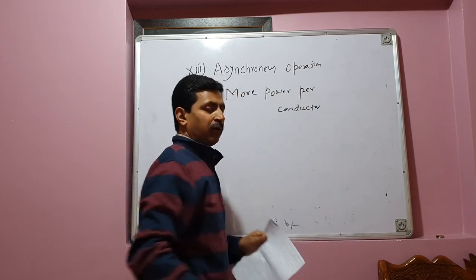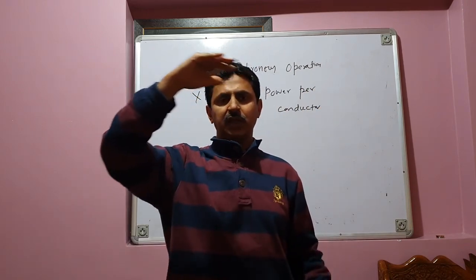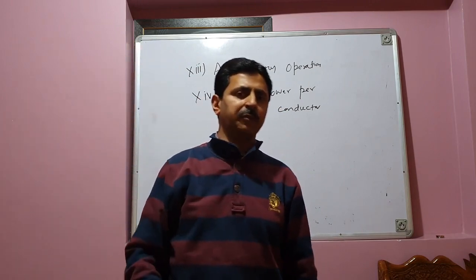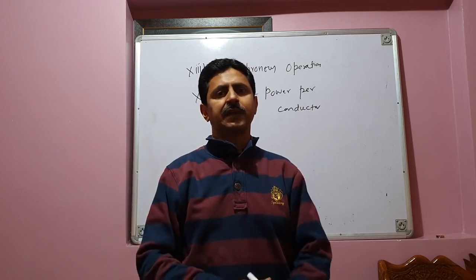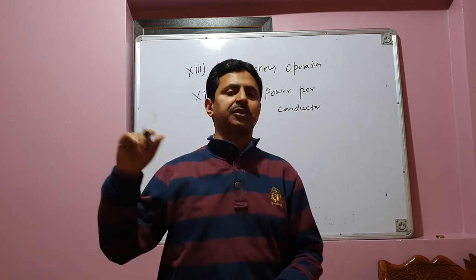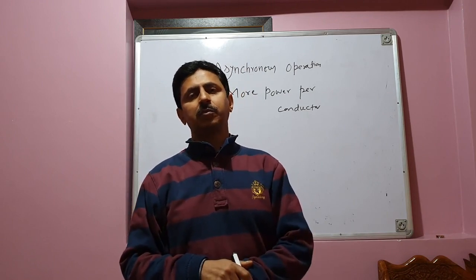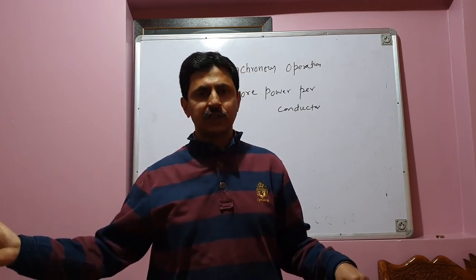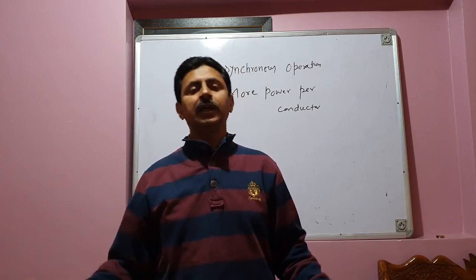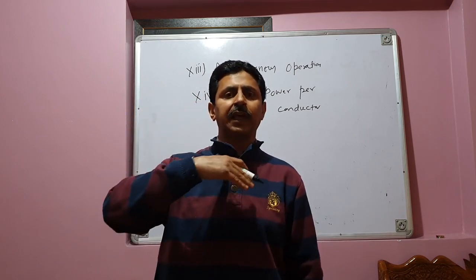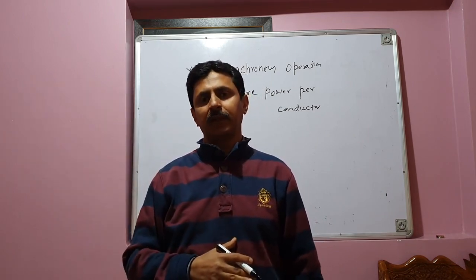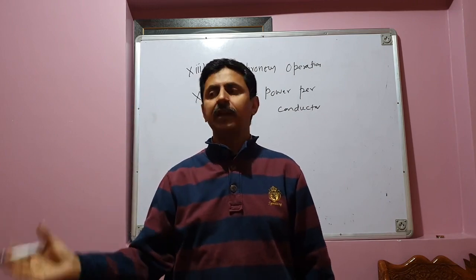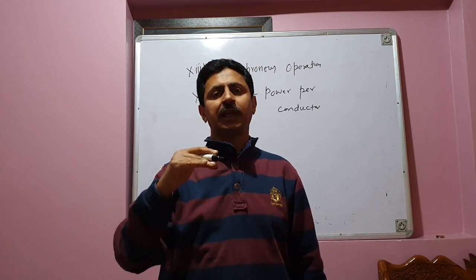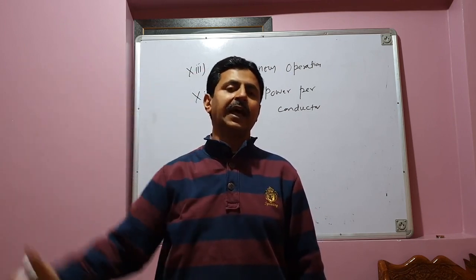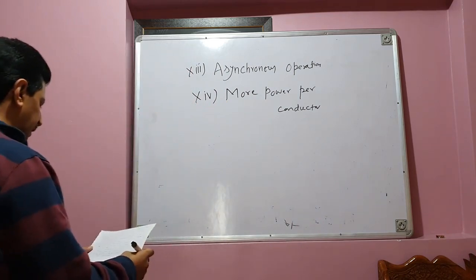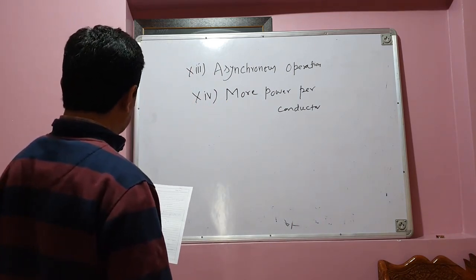I have already told you that in AC transmission there is a limitation because of stability, and line reactance puts a limitation over the amount of power that can be transmitted over the line, and you can never load the transmission line up to its thermal limit. That is not the case with HVDC power transmission system. Length is not a constraint and stability issue is not there. Therefore, you can load the DC transmission line to its maximum limit, which is called the thermal limit. So if you compare a DC transmission line with an AC transmission line, in case of DC the power per conductor is quite high compared to AC. This is yet another significant advantage of HVDC power transmission over AC power transmission.